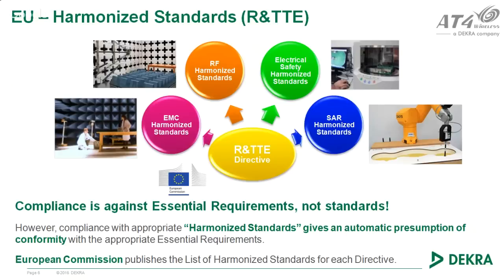For a typical radio product, you need to test EMC, and you need to test radio frequency to verify that the modulation, powers and bands used are okay. You need to test electrical safety to verify that the product is not dangerous for persons. And depending on the use of the product, you need to test SAR or not. With SAR testing, what we measure is the radiation when the product is close to the body, for instance a cell phone that I can carry in my pocket, or hold in my hand close to my head, that it does not cause any risk for the user, okay?